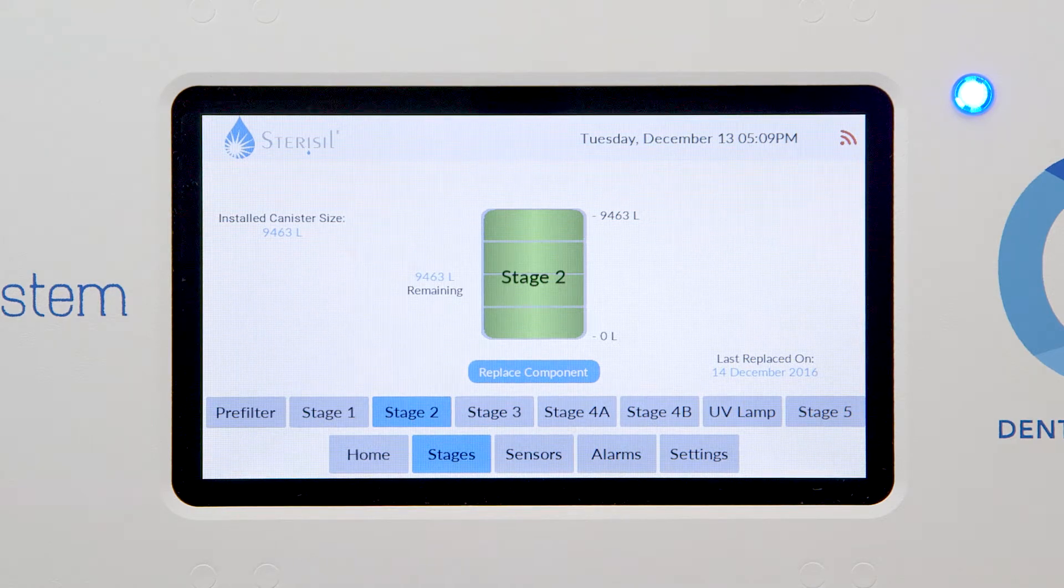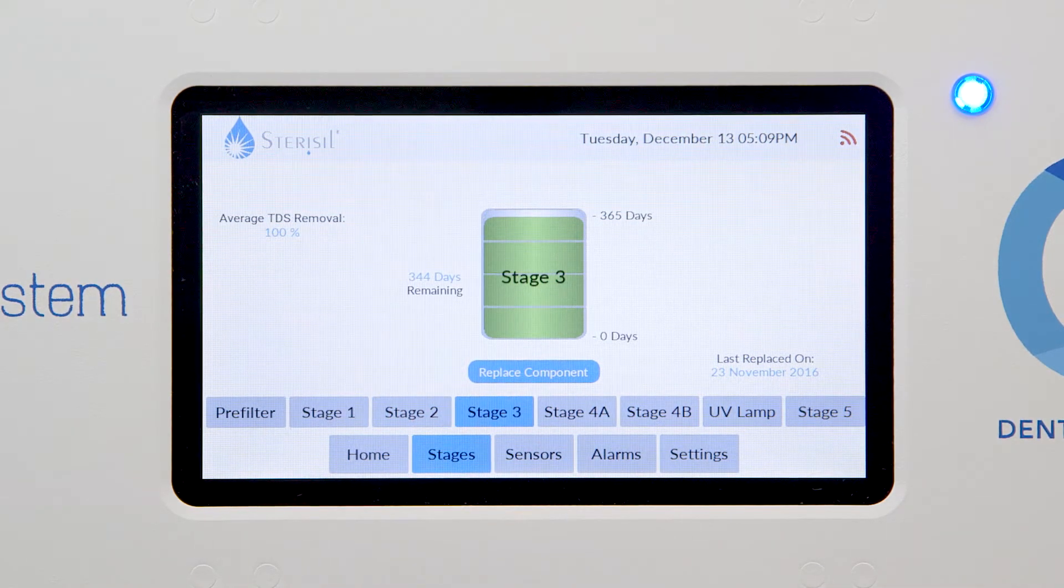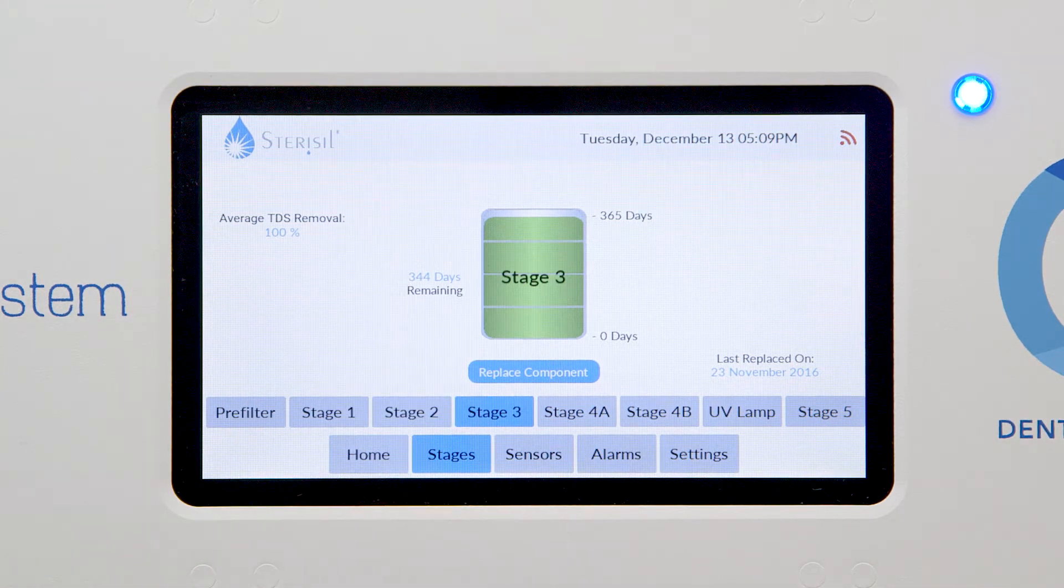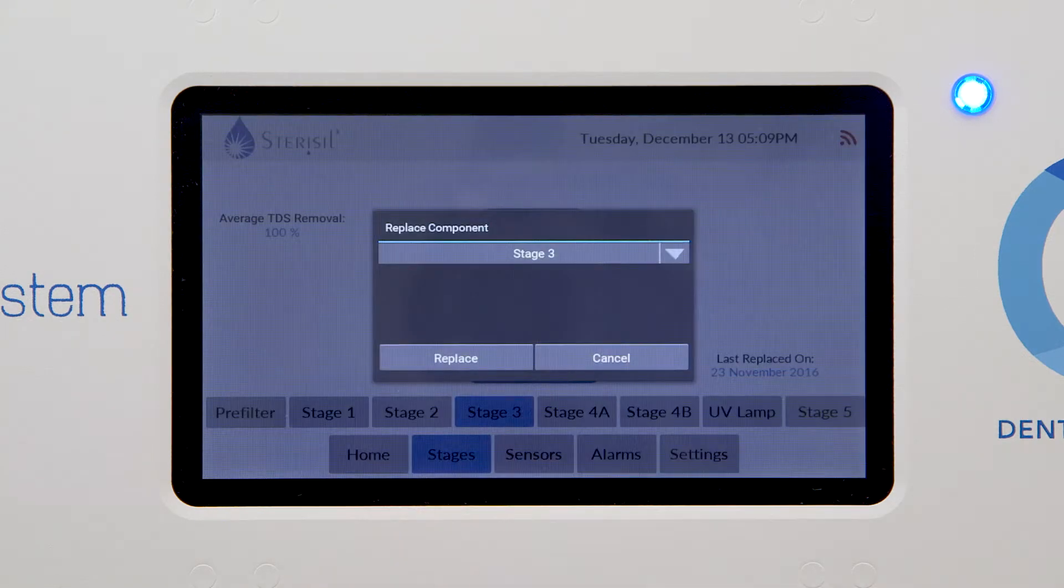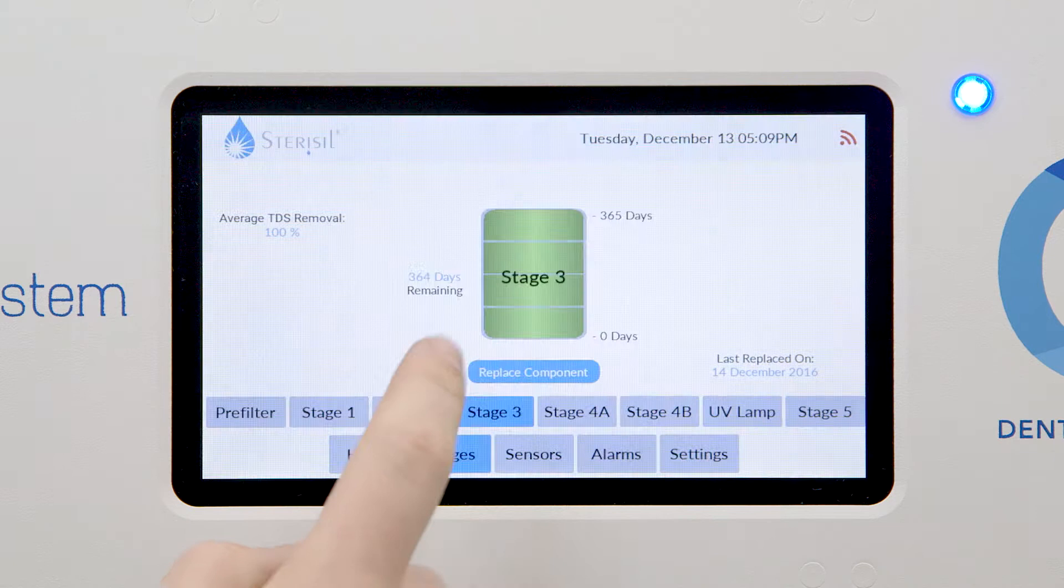Stage three's lifespan is based on either a 364 day count or the TDS water quality coming off it. If the counter on stage three is not reading 364 days, select replace component, then touch stage three from the drop down menu, and touch replace.